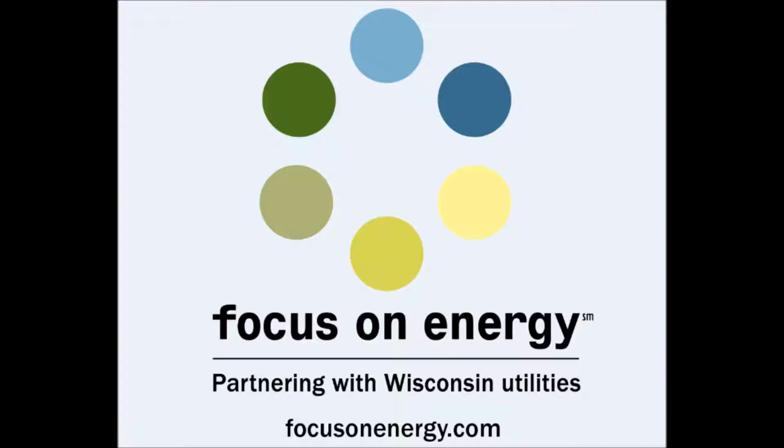A couple of other quick things I want to touch on are heating systems, whether it's a unit heater in a greenhouse or a shop. Make sure you're doing an annual checkup, and if it seems that your unit heater is not running efficiently, maybe you need a combustion efficiency test done on your furnace. Any belts or valves, nozzles, fuel filters, all those things should be looked at on a regular basis.